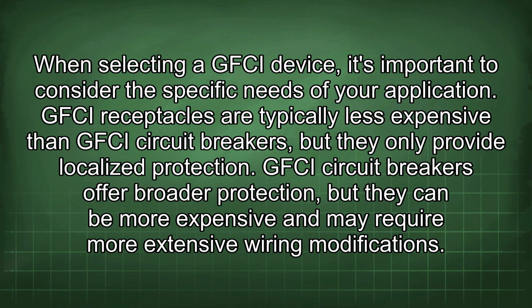When selecting a GFCI device, it's important to consider the specific needs of your application. GFCI receptacles are typically less expensive than GFCI circuit breakers, but they only provide localized protection. GFCI circuit breakers offer broader protection, but they can be more expensive and may require more extensive wiring modifications.